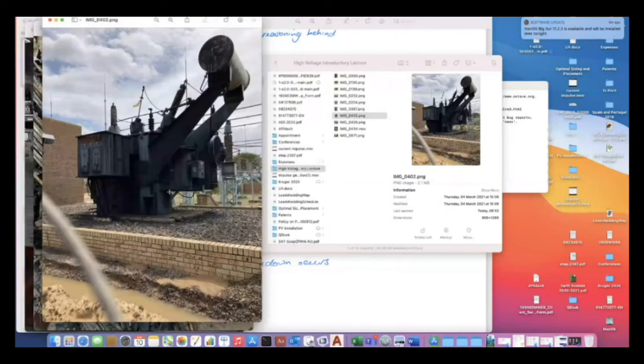There's another example of what happened when it went wrong. At the top there, I spoke about a bushing. In this case, the bushing actually arced and exploded. You can see that the bushing is no longer there. You can see all these black streaks down the side. That's caused by damage from a fire and from oil.